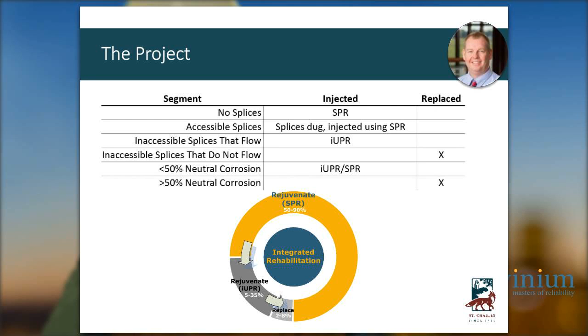Through that, the little circle here, depending on subdivision, most of the spans were able to rejuvenate using the sustained process. Based on how people installed cable in the 60s and 70s, where they would put a trencher in the ground and run the cable in the trench, and then at the end of the cable they'd direct bury a splice and just keep going, we had ended up with a lot of splices, and in a lot of the neighborhoods, they were very difficult to dig up. So we did end up with a significant number of unsustained injection spans. And then there's about 10% of the spans that you end up just not being able to inject due to either inaccessible splices that don't flow or corroded neutral.